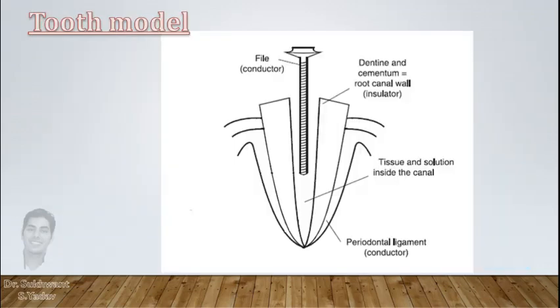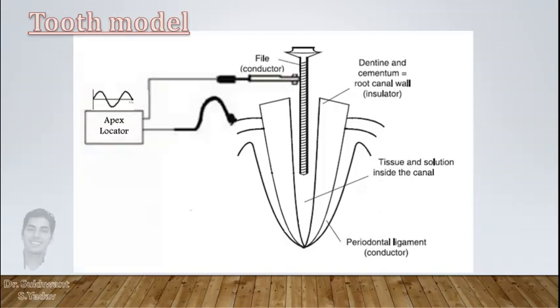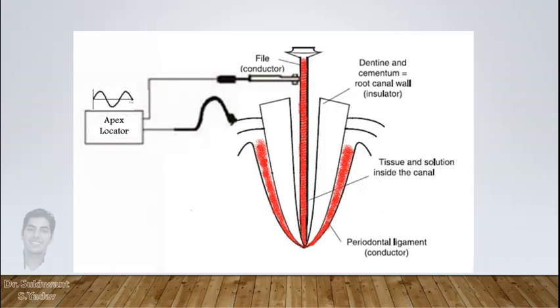When a file is inserted in root canal and attached to voltage in apex locator, periodontal ligament and stainless steel file act as conductors. As file proceeds in canal to apex, both conductors touch each other and circuit completes. This leads to flow of current in periodontal ligament and resistance recorded.